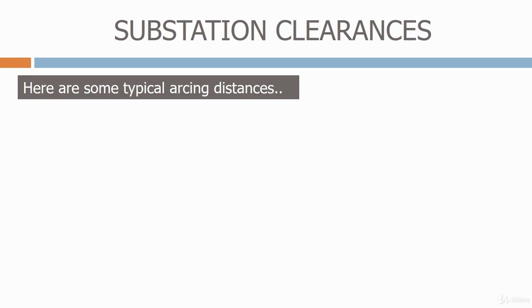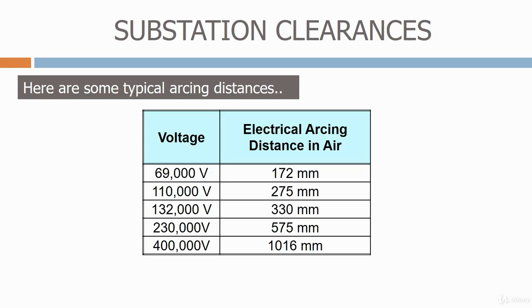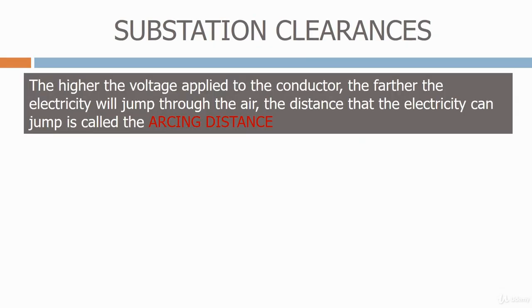Here are some typical arcing distances. As you can see, as the system voltage increases, the electrical arcing distance in air also increases. At 69,000 volts or 69 kV, the electrical arcing distance in air is 172 millimeters. When we go up to 400,000 volts or 400 kV, the electrical arcing distance is over a meter. The higher the voltage applied to the conductor, the farther the electricity will jump through the air. The distance that the electricity can jump is called the arcing distance.